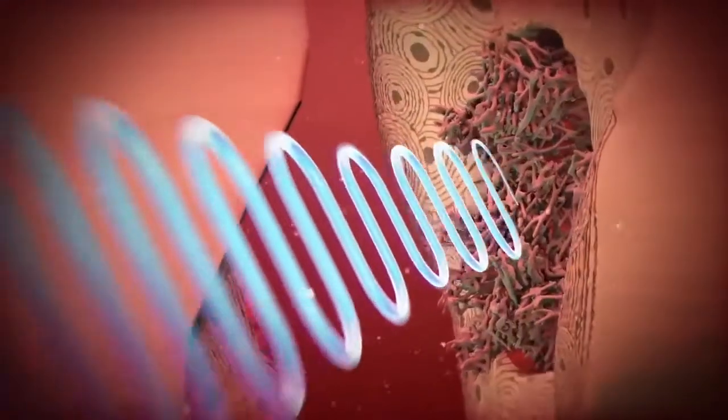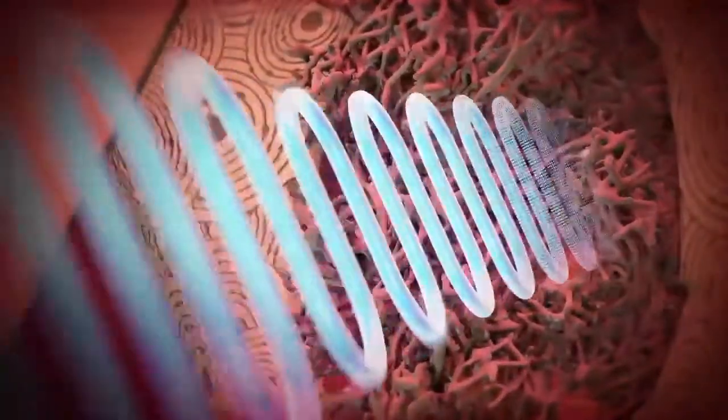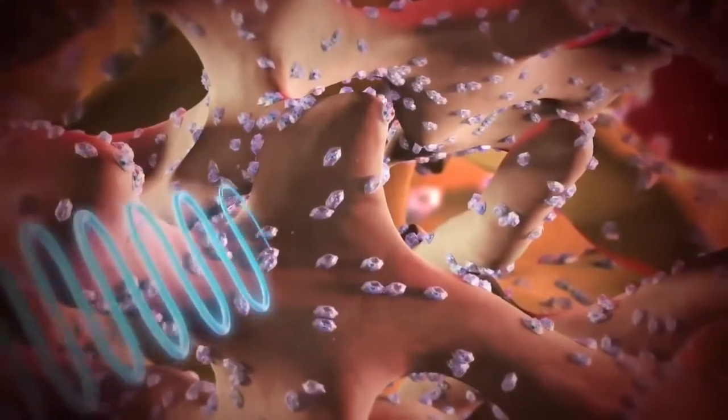The CMF Bone Growth Stimulator is unique in that it delivers an electromagnetic signal that continuously operates within frequencies optimal to heal bone. The patented combined magnetic field produces a consistent frequency of 76.6 Hz.